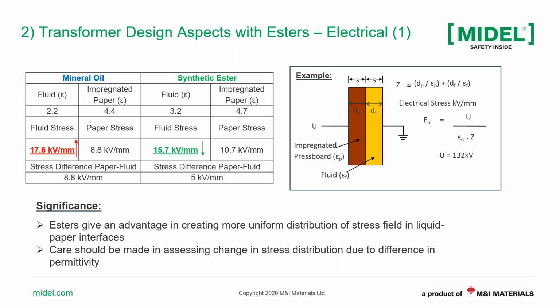So in this, let's focus first our attention on the table. You see mineral oil and synthetic ester. Underneath it, you have the fluid permittivity. For mineral oil it is typically 2.2. And if you impregnate paper with mineral oil, the composite system has a permittivity of 4.4. Comparing this with a synthetic ester, the fluid permittivity is higher than that of mineral oil, 3.2. And then, with the paper impregnated with synthetic ester, the permittivity is 4.7.